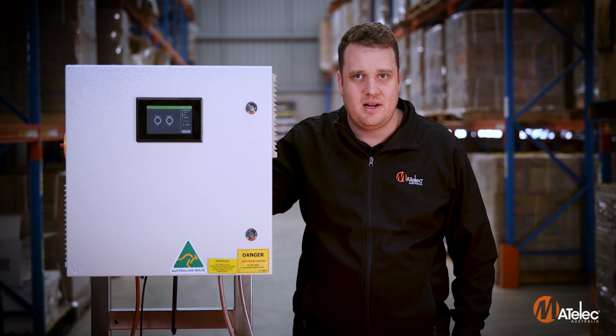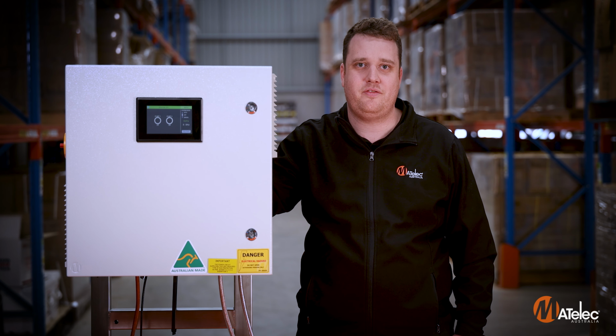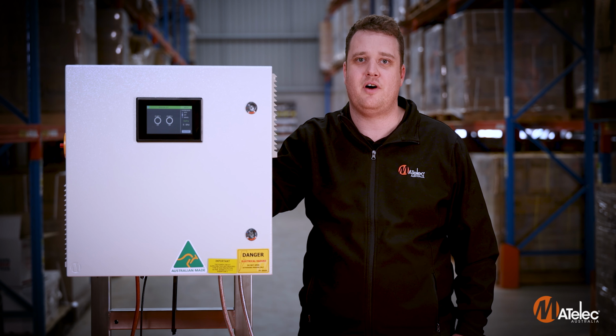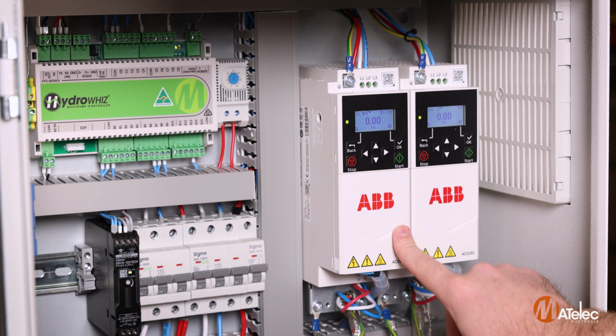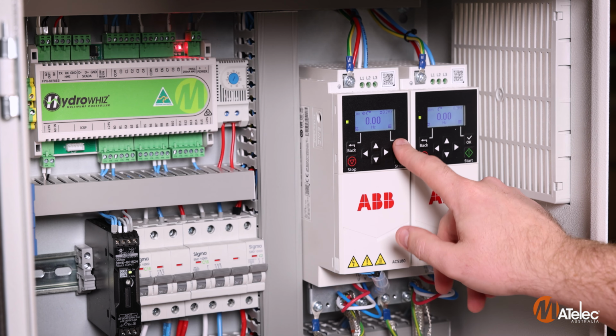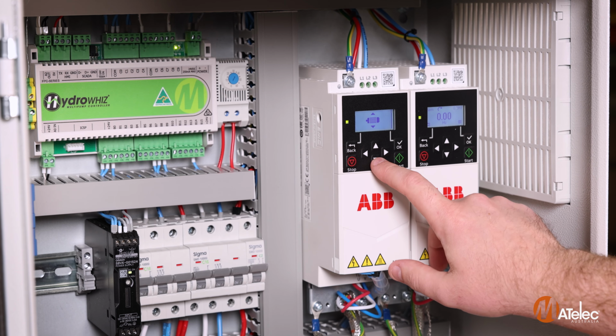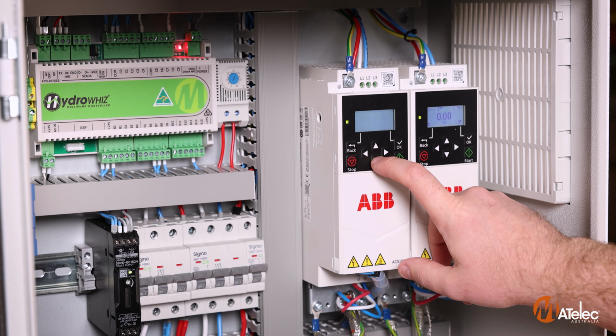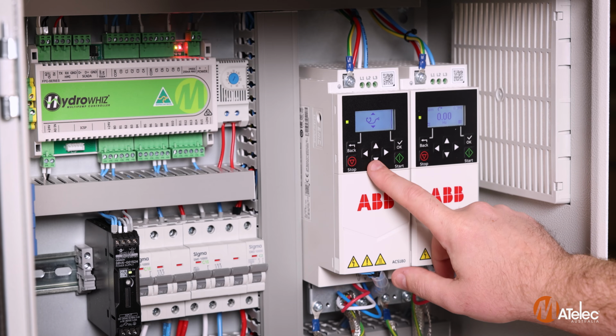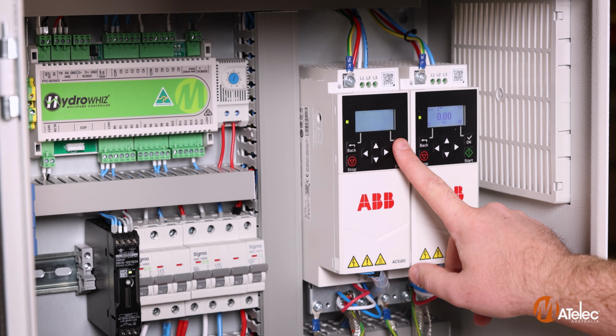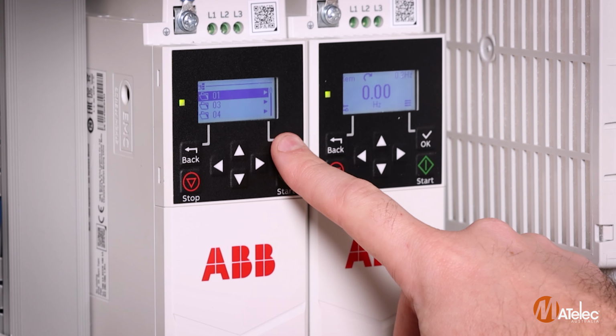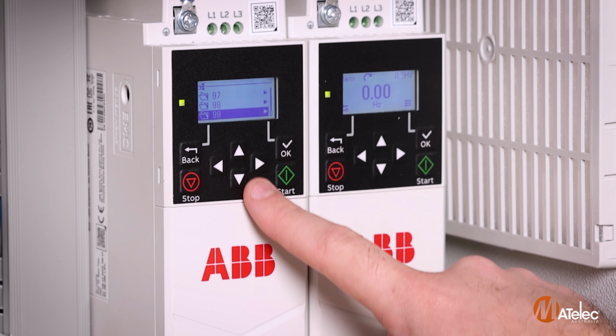The ACS180 drive includes a built-in interface screen which we use to define the pump parameters for the motor connected to the controller. From the home screen, press the OK button to access the main menu. Now, use the arrow keys to navigate to the bottom option, Parameters, and press OK. Then, navigate to Parameter section 99.